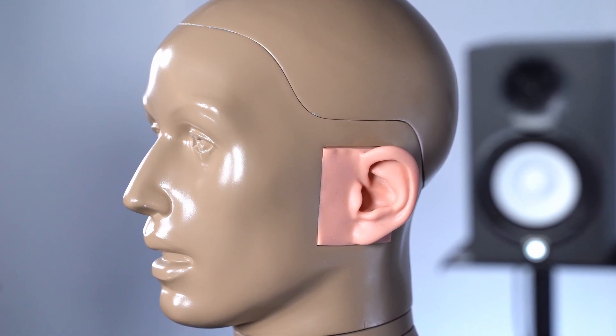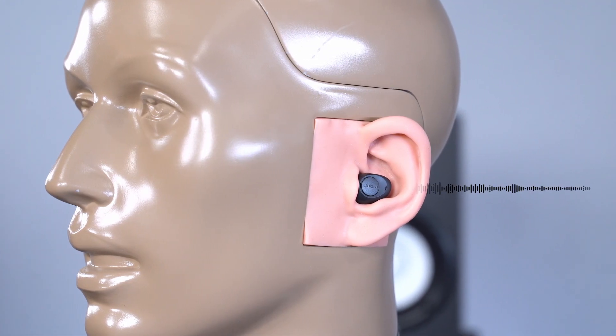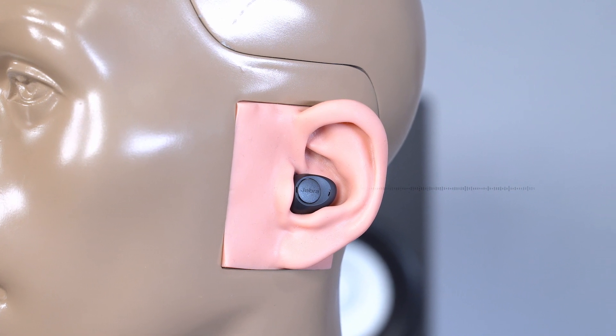Say hello to KEMAR. KEMAR is no ordinary mannequin — it's our anthropomorphic acoustic mannequin, which is a really fancy way of saying he's designed with accurate human characteristics. KEMAR has lifelike ears with microphones instead of eardrums, designed specifically to test hearing instruments. KEMAR records sound from the environment while wearing hearing aids, so when you hear those recordings, you're hearing exactly what KEMAR hears from his ears.